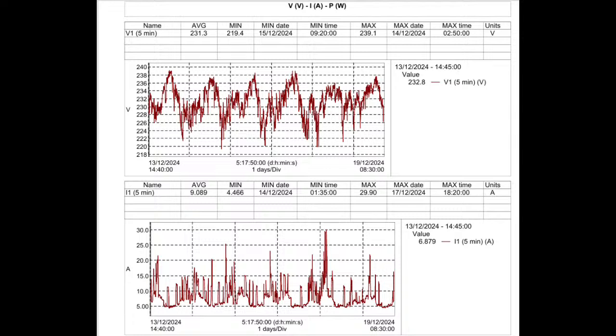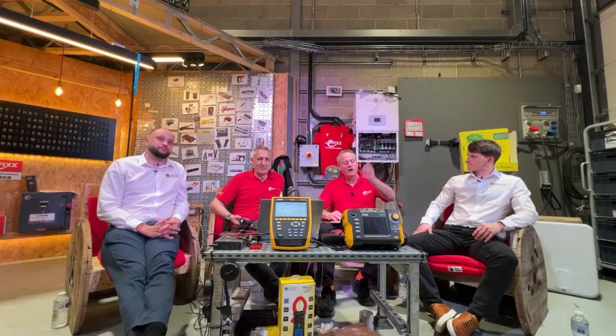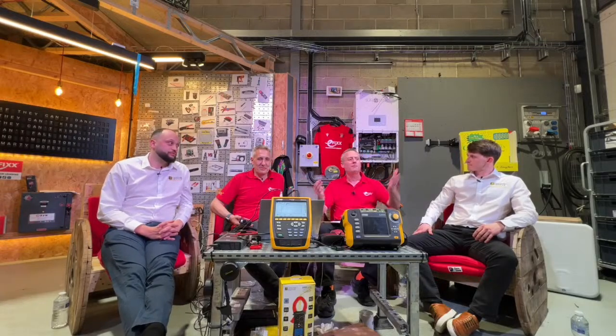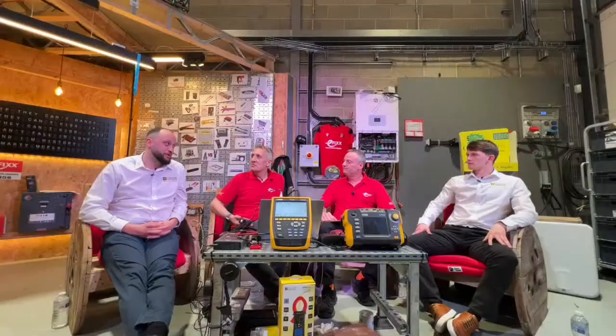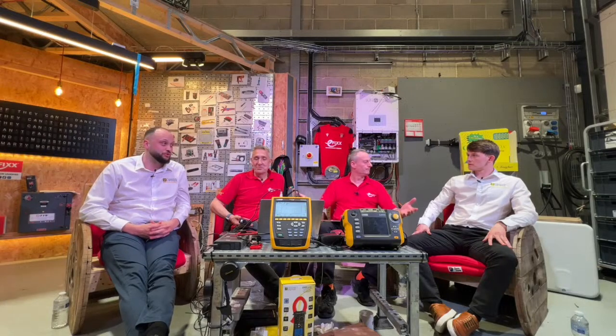So this is a dwelling, an electric dwelling like we all have. We do all these calculations per BS 7671, looking at on-site guides and guidance notes, and we come up with a horrific number. Rick's going through his course at the minute - he'll get maximum demands above 60 amps. So with a 60 amp fuse, he'd be worried to death it would be operating at 29, 30 amps maximum, over a 5-minute period as a maximum for that single phase incoming feed. That was the maximum load on that house.